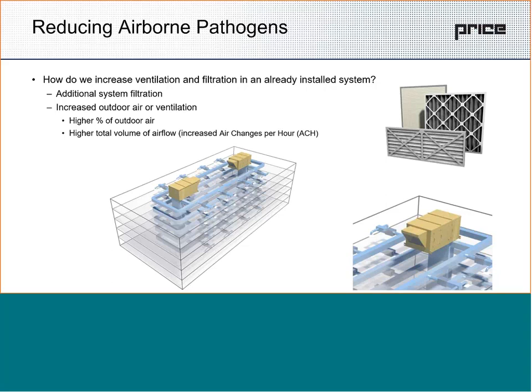So you want to find a way to get that increased filtration. The other suggestion for dilution would be increasing the amount of outdoor air. We're finding that people are running into the same situation where they're not able to increase the amount of outdoor air because the air handlers aren't capable of conditioning additional outdoor air. If you have the ability to increase filtration, I would strongly recommend it. It's what ASHRAE recommends as your first change to the HVAC system in a building.